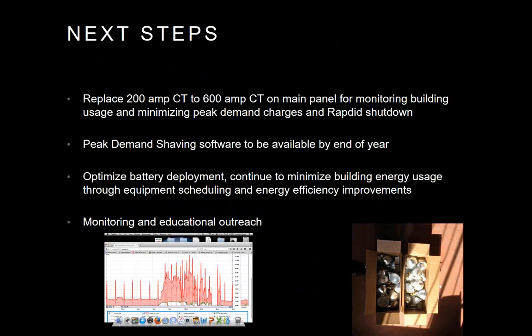Another thing is that we're currently monitoring the battery, which is connected with a 200 amp CT device for monitoring building usage. In the next month or so, we should be getting a 600 amp CT, which is what we need to actually measure all of the building's energy use. Right now we're just measuring one of the sub panels, which doesn't have the ground source heat pump on it, so we'll be able to more accurately schedule the battery once we have that 600 amp CT.